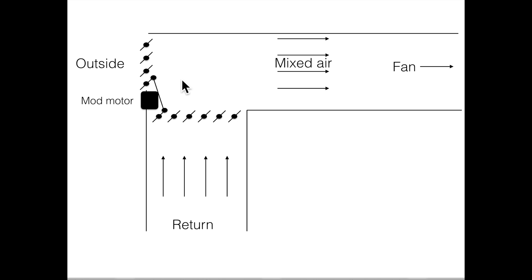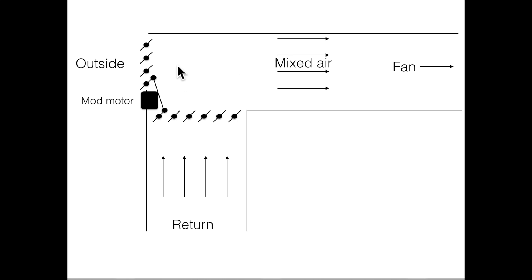So if I open it up wider, and of course this is assuming outside air temperature of 45 or 50, the more I open these up, the more these are going to close, and so the larger percentage of outside air is coming in, so the mixed air is going to be cooler.